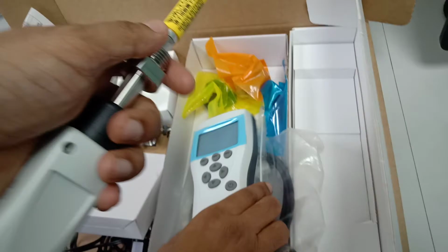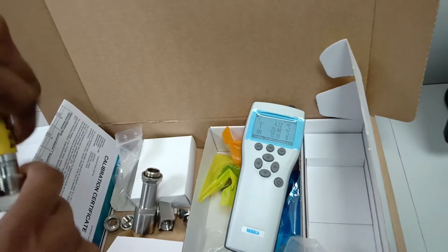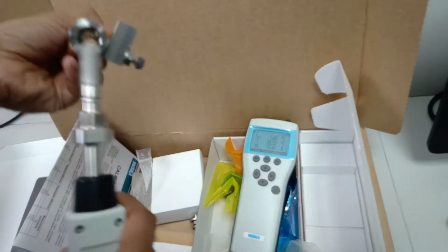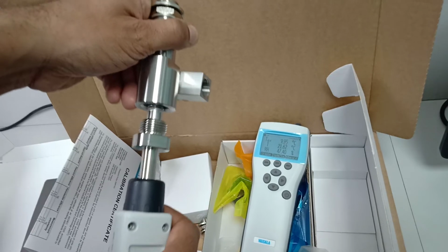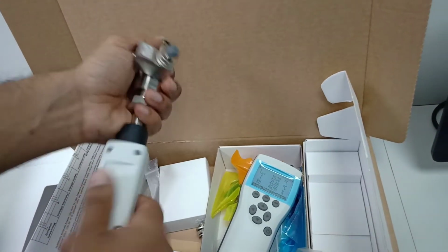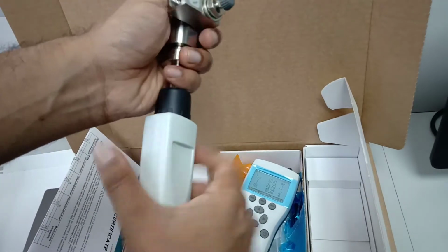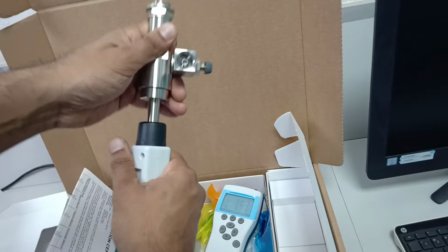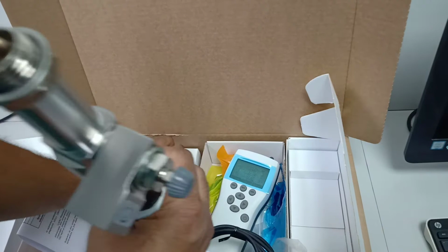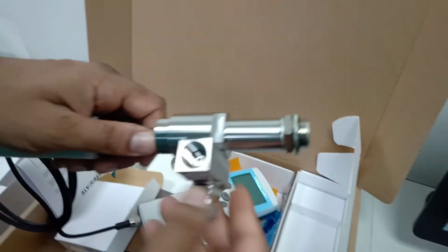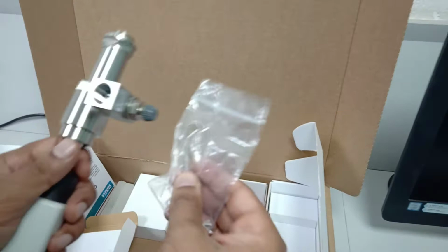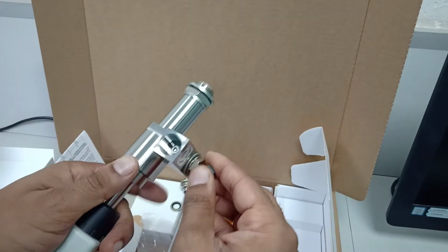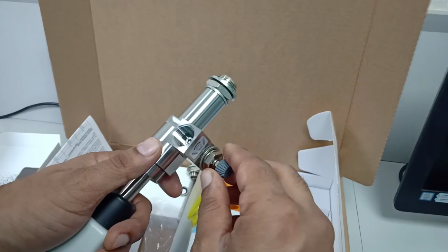So now I will show you how to connect it to two pressure sampling cell, which is used in SF6. Remove cover. So this is the sample cell. It is called two pressure sampling cell. Just tighten it up. You tighten it up, and from here you have different adapters. These are the different adapters which you can use as per your process. You put the adapters in your GIS for SF6 dew point measurement, and this is the leak screw. So this is adjusted using the Allen key. So for the minimum leakage, you just draw a minute amount of SF6 and it will readily measure the dew point.